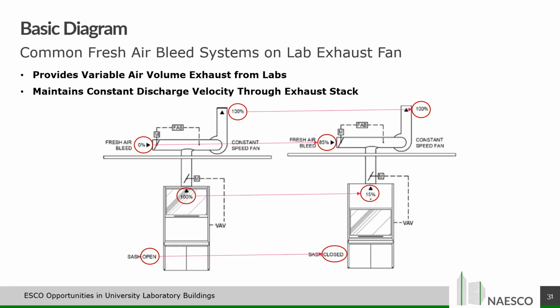It's something called a fresh air bleed system on your exhaust fans. And this allows you to do variable volume control in a lab while maintaining constant discharge from your stack. So on the left here, again, very simple diagram, but we've got a single fume hood here. It's a VAV fume hood. There's a damper in the exhaust stream, which will be used to control the exhaust volumes. Up here, we've got a fresh air bleed damper on the roof, and we've got the discharge from the stack.